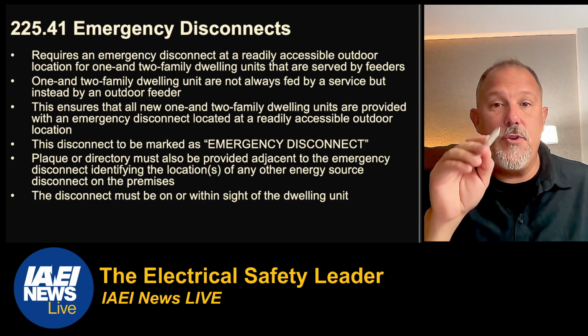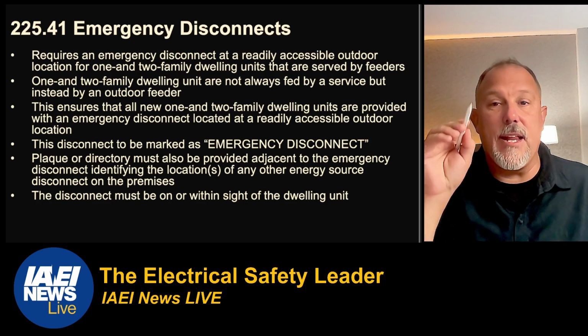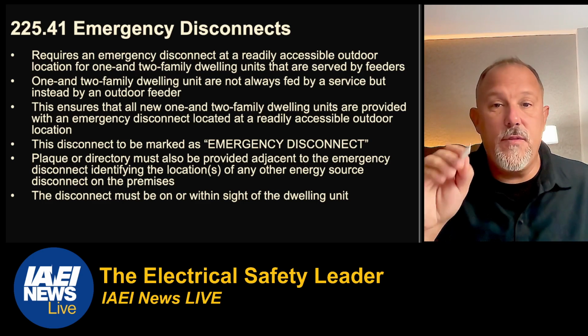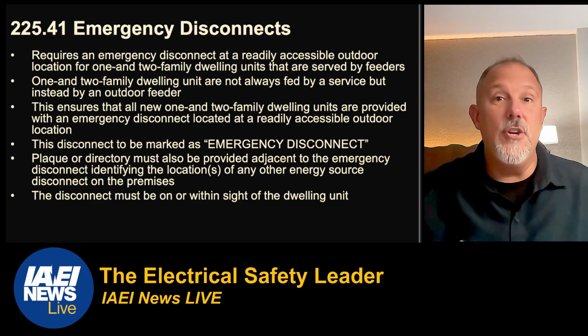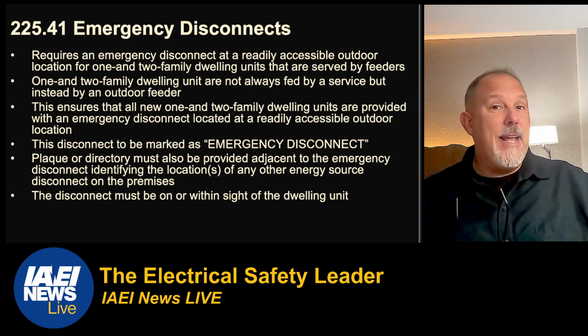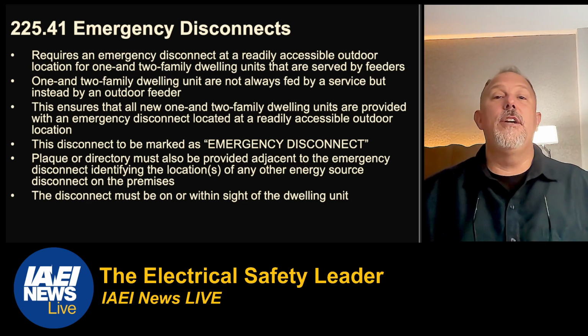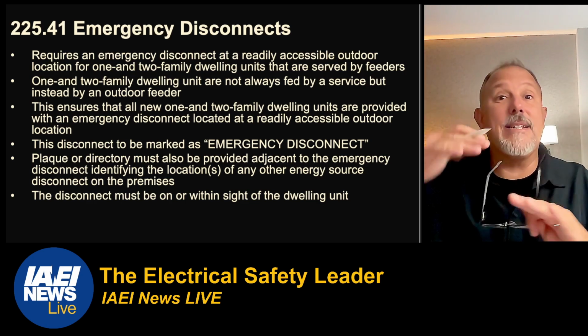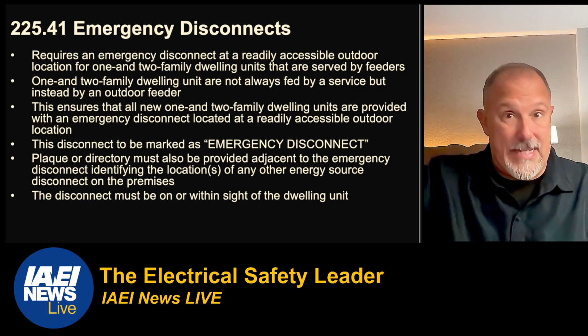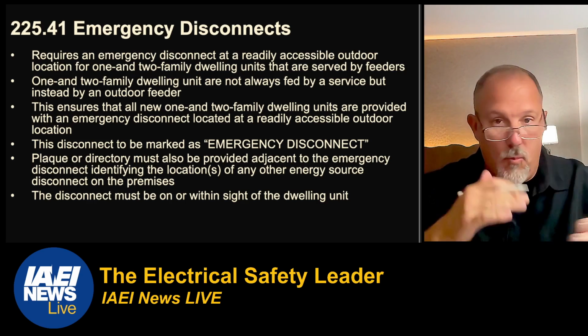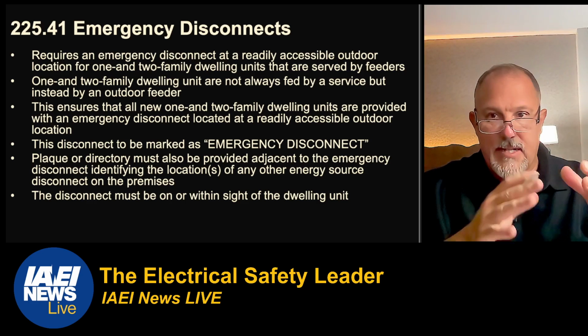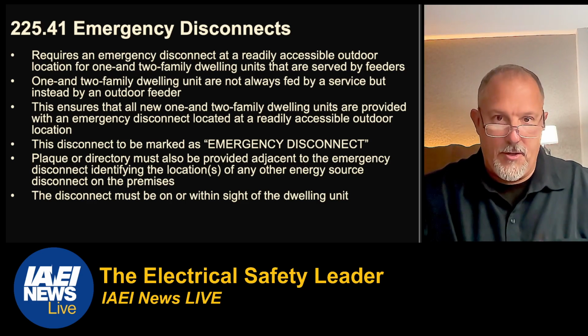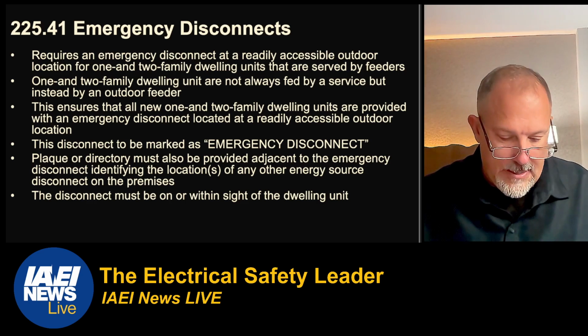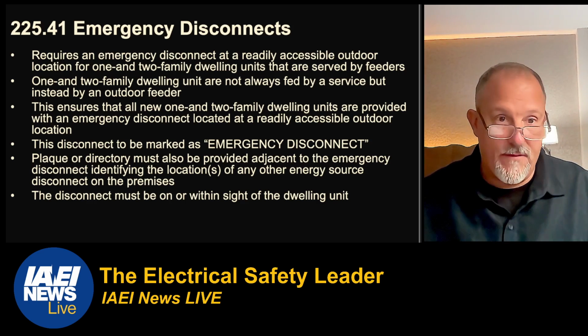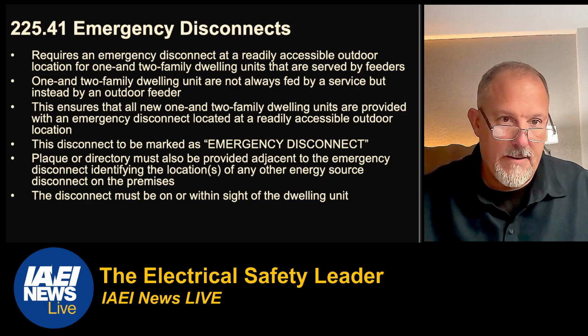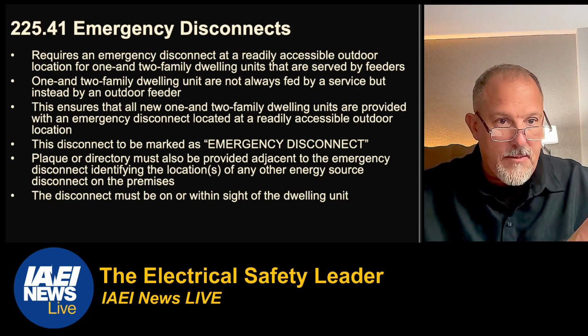And it says you have to have an emergency disconnect at a readily accessible outdoor location for 1 and 2 family dwellings that are served by feeders. So you have the services in 230 and these outside feeders in 225 to address that scenario where the service is out there at the road, for example. And they want it readily accessible at that dwelling unit. So that's sort of what they did in 225.41. All right, so the emergency disconnect is important.